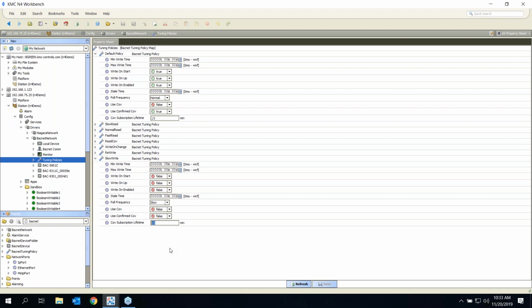Once we send that subscription request, the device will respond with a value, and then it's up to the device to tell me whenever that point value changes during the next 15-minute period of time. So instead of me having to send a read request, the BACnet device just pushes notifications to me when the value changes. That can be more efficient than a request and polled response scenario. That's what COV subscriptions are designed to help with, the polling time on the network. We will renew the subscription at half the lifetime, so at 7.5 minutes, we renew the subscription.